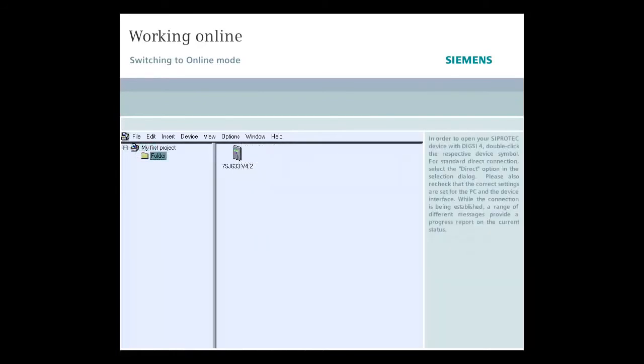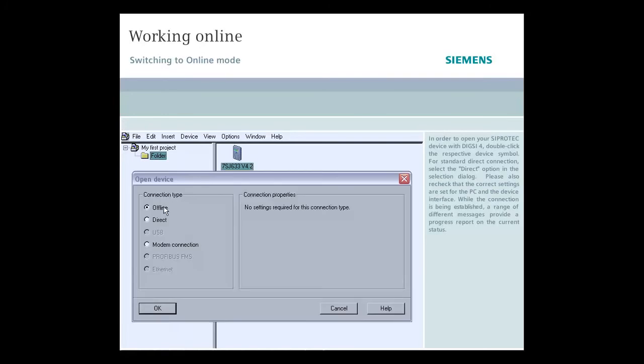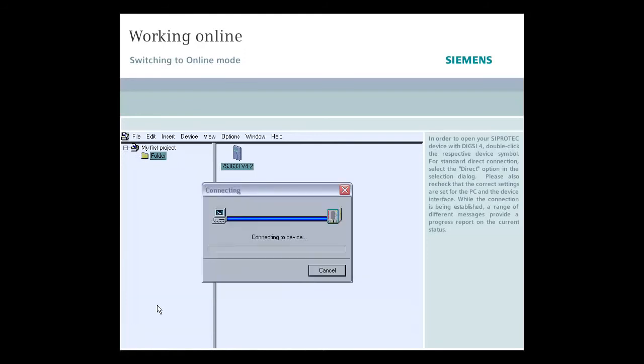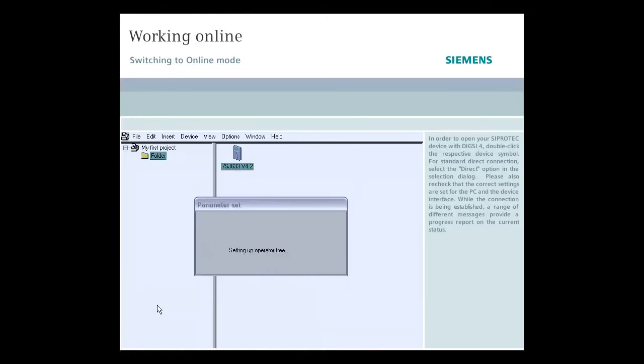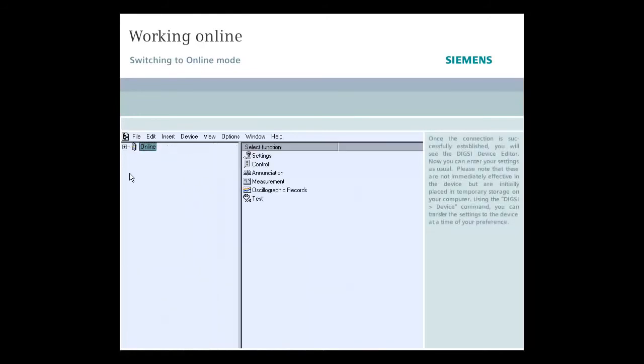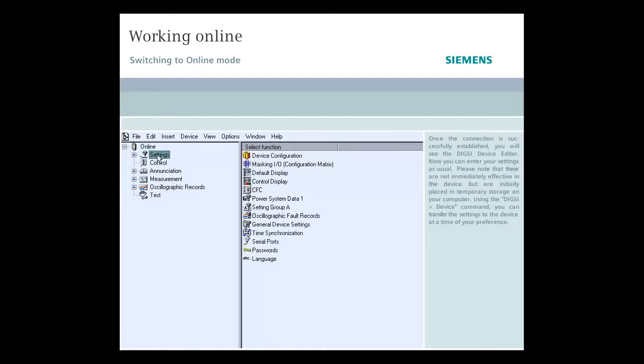In order to open your SIPROTEC device with DIGSI 4, double-click the respective device symbol. For standard direct connection, select the Direct option in the selection dialog. Please also re-check that the correct settings are set for the PC and the device interface. While the connection is being established, a range of different messages provide a progress report on the current status. Once the connection is successfully established, you will see the DIGSI device editor.